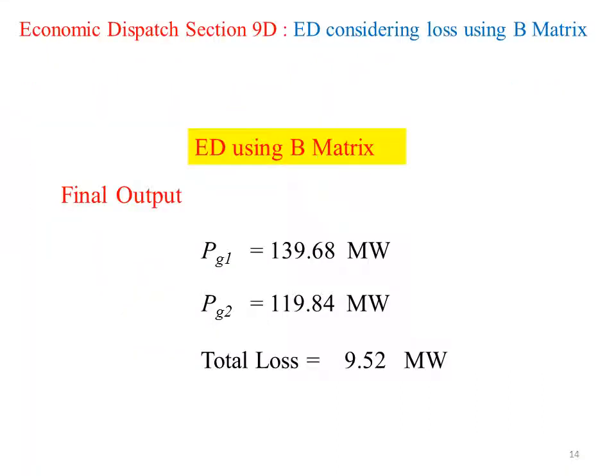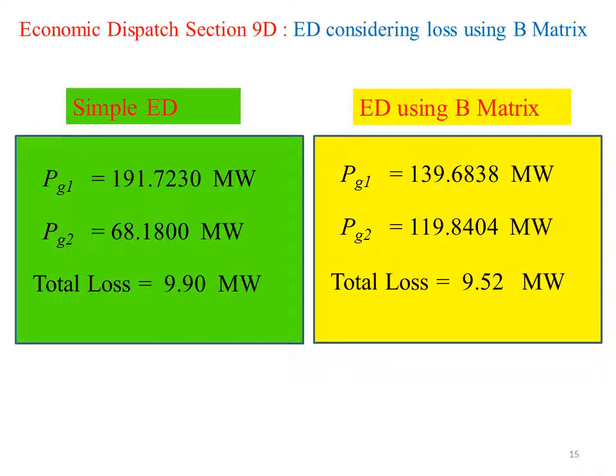The power loss should be 9.52 megawatts. Let's compare the output from two methods. The total loss from simple economic dispatch without loss consideration is 9.9 megawatts, whereas the total loss from economic dispatch with loss consideration is 9.52 megawatts, which is approximately 0.4 megawatts less, or approximately 4% power loss reduction.